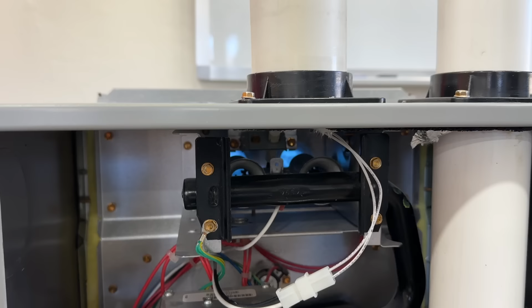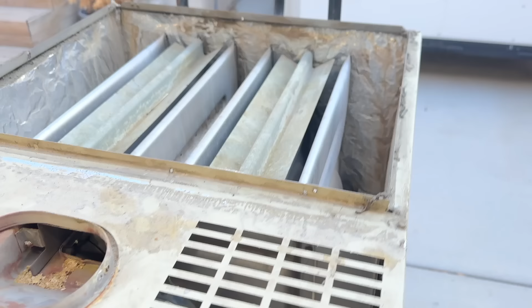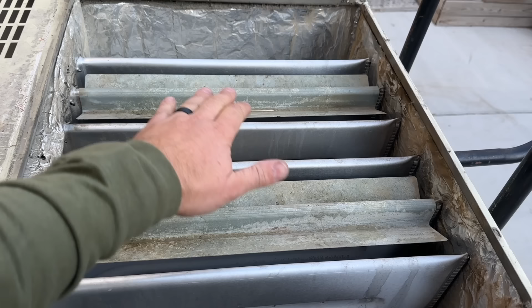Now, I wanted to mention something else here. When your burners turn on and they run, as you heard, the fan just turned on. And that's a good time to be watching the flames to see if there's any orange presence when the fan comes on. Now that's in addition to the test that we're about to do, but just something that you can be aware of. If when your blower does come on, you see a ton of orange in one of the burners, that's a great indicator that you do actually have a leak. There it goes. And we have nice and hot air coming out from the heat exchanger area here.